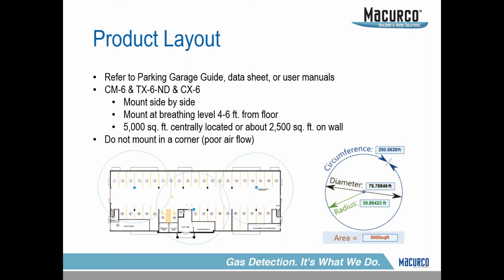Most of the time we want these things mounted at breathing level, so 4 to 6 feet. If you go to our competitors, some will say they want NO2 up at the ceiling but CO at breathing level. CO and NO2 actually disperse evenly in retrospect. NO2 comes out super hot so it rises, but by the time it gets to your nose and mouth, the air has cooled that gas down enough that it's slowly trickling up. So our gas detector, if it's sitting at 4 to 6 feet, that's what we care about — we don't care what people are breathing at the ceiling. That's where you'll see that differentiation on our data sheets.